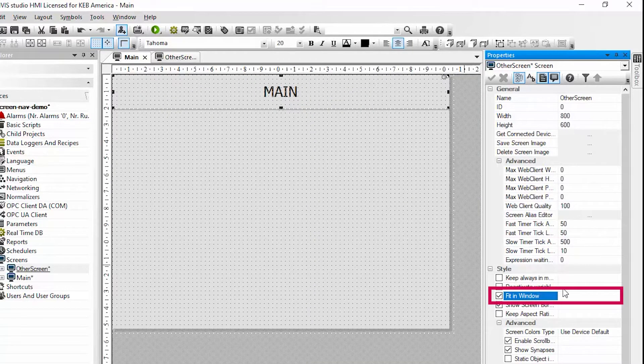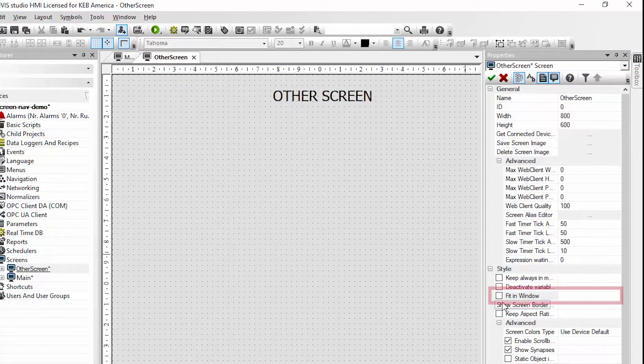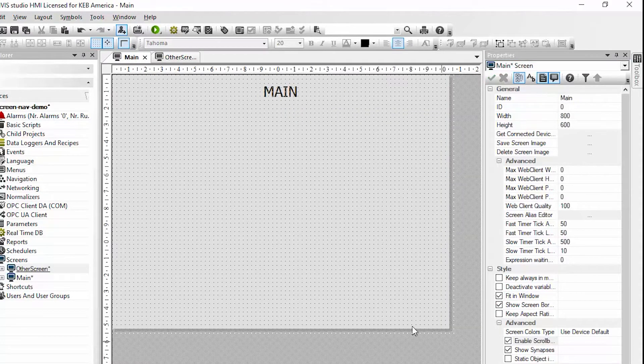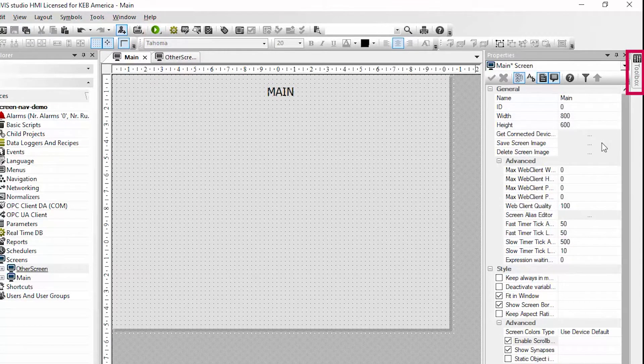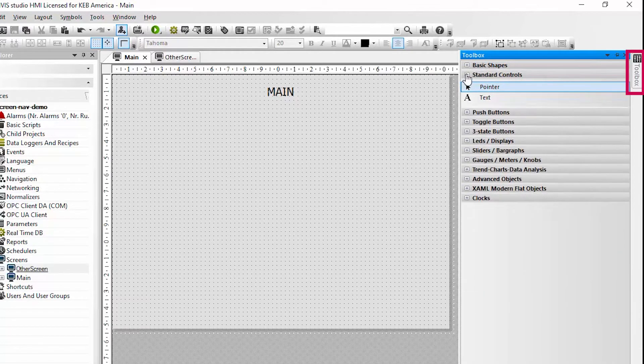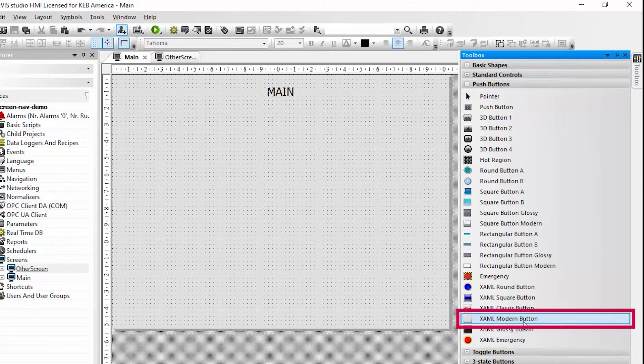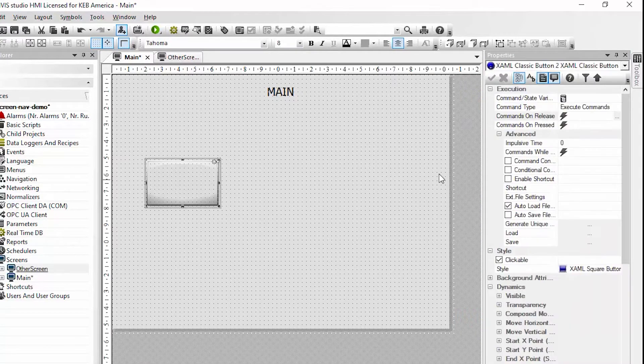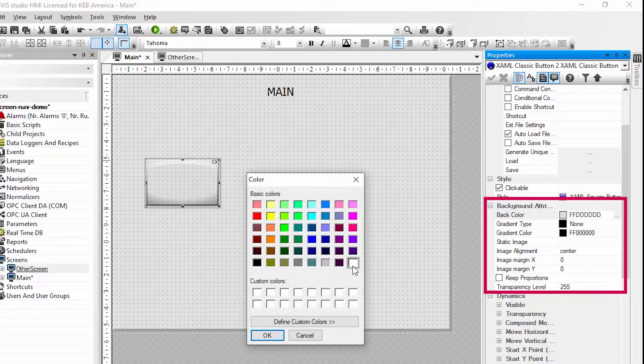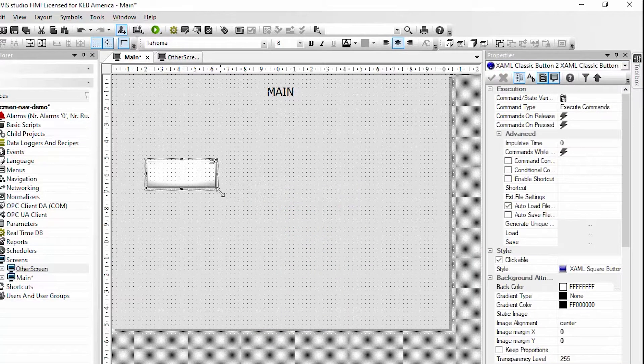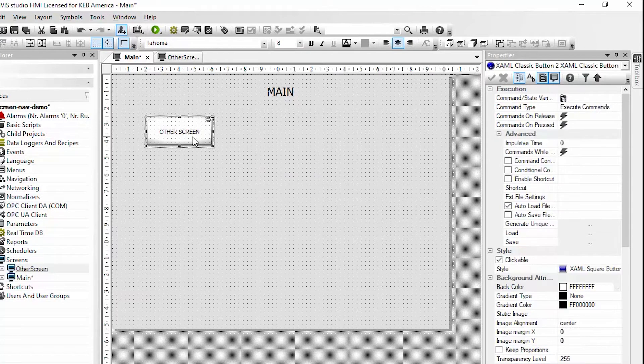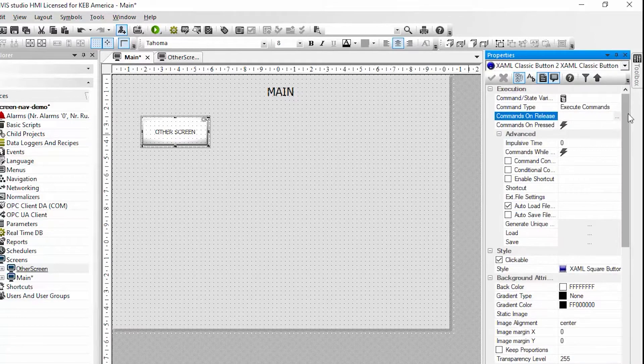I'm also going to disable the fit in window property on each of my created screens and this will keep the aspect ratio locked when we go to simulation mode. So to navigate between the two screens I'm going to use a push button. I will go to my toolbox, push buttons, and I will use an XAML modern button. To make it stand out I'm going to make the background color white and I'm going to label it other screen. The most common way to change screens is by pressing one of these push button elements and executing a command.